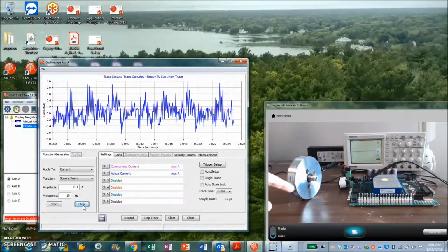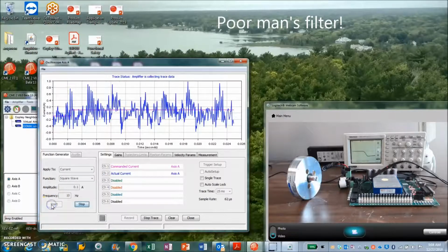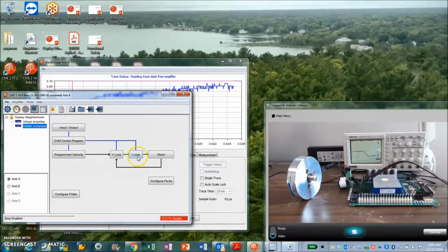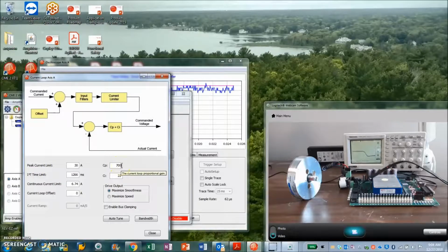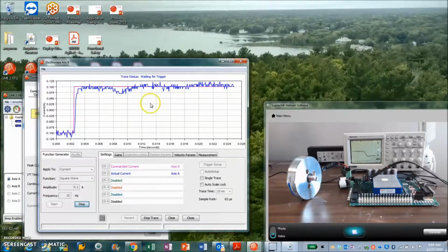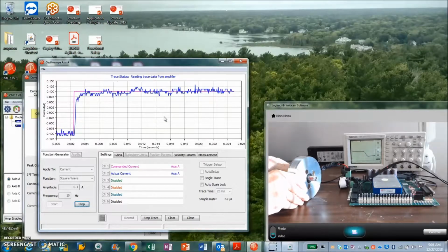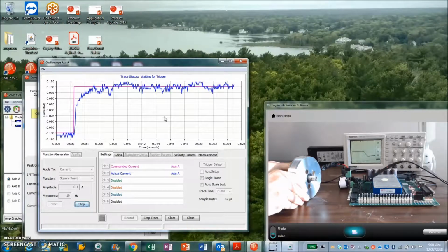One advantage of the inductors is the reduction in the noise emission. I don't want you to worry about using a Copley for inductive noise, because Copley's rise times are at least 5 times better than the competition. So now with the added inductance, we can see much better current loop tuning capability, commanded and actuals much better, and there's no runaway condition possible.